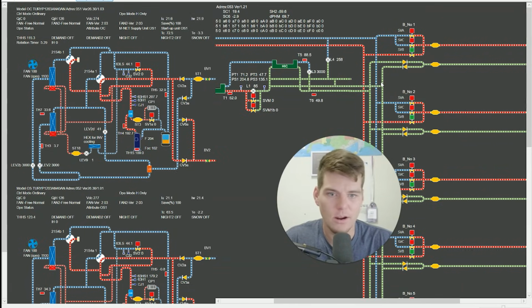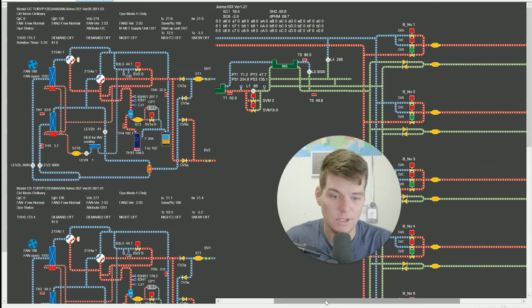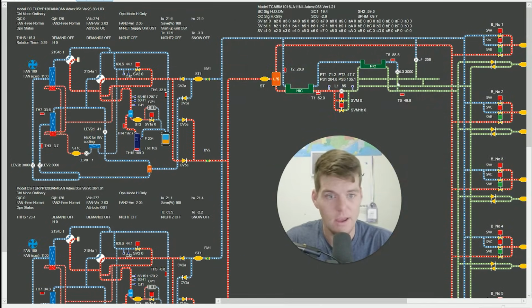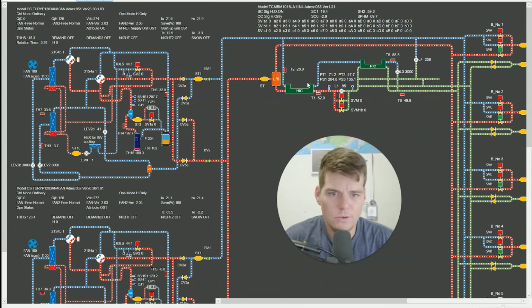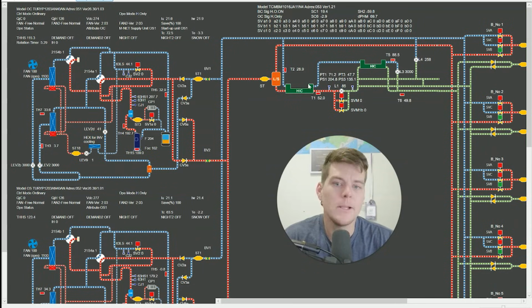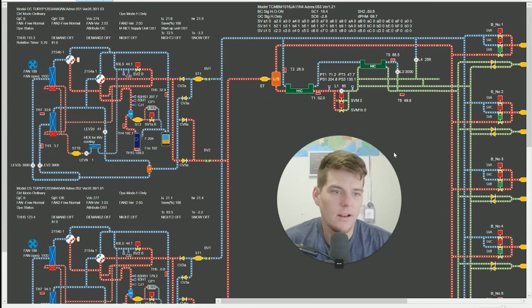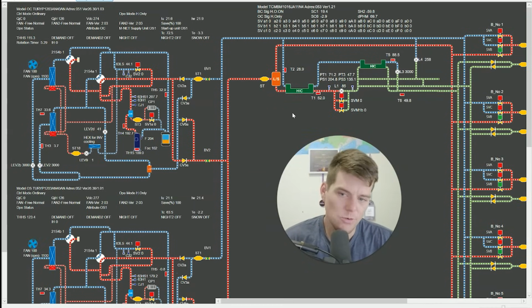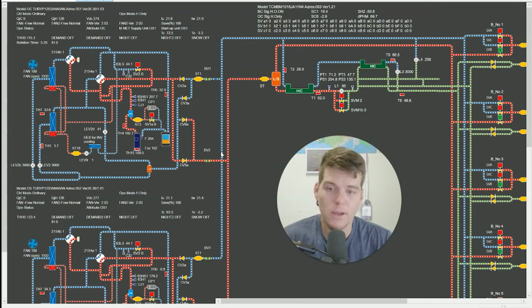We also see here with this liquid coming back, we've got 258 pulses, which looks like that bypasses the box itself. That comes up and across here. That looks like that's making vapor to come back here, or maybe going through dual subcoolers to feed back over here. These colors do get a little confusing, not understanding the magic that is Mitsubishi, but I'm sure someone will easily point that out in the comments on this video. But for the most part, we know that what we're making liquid to go where? To go back to the outdoor unit to do what? Well, to turn into a vapor for our compressors.